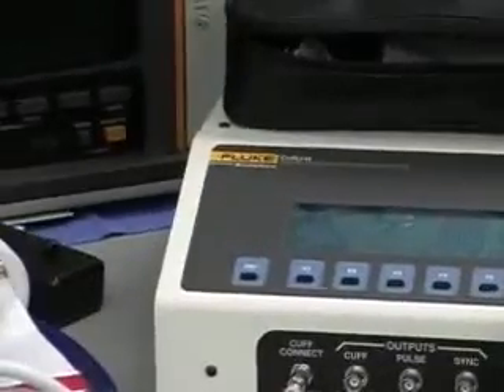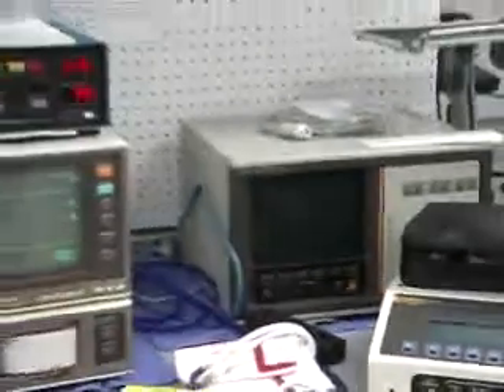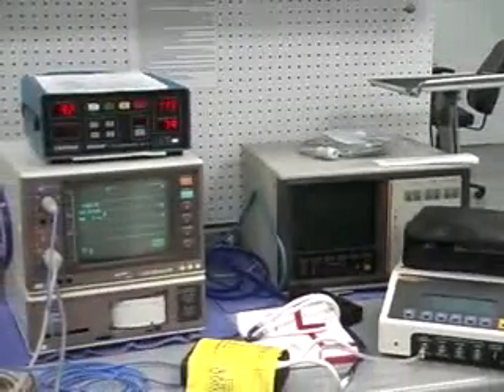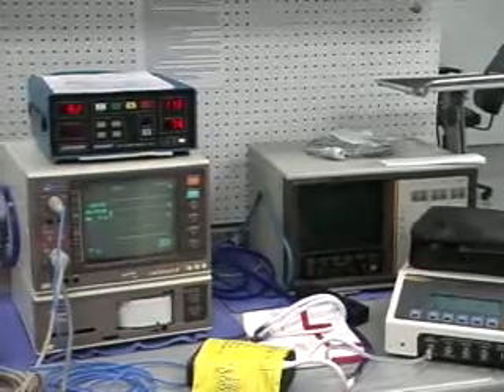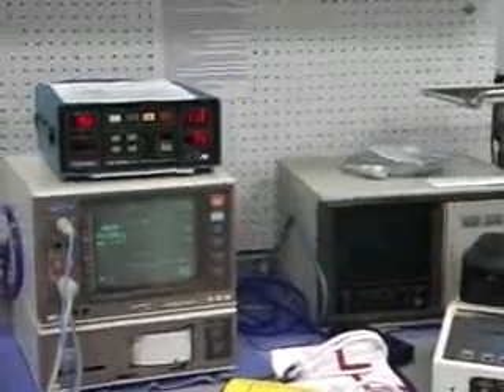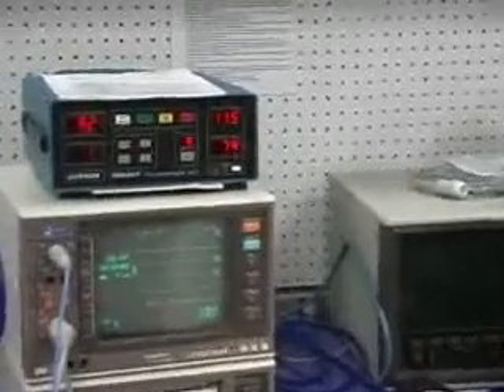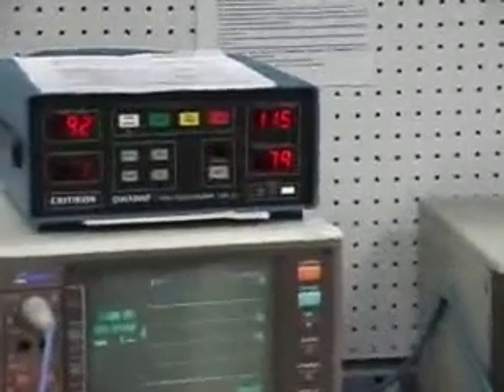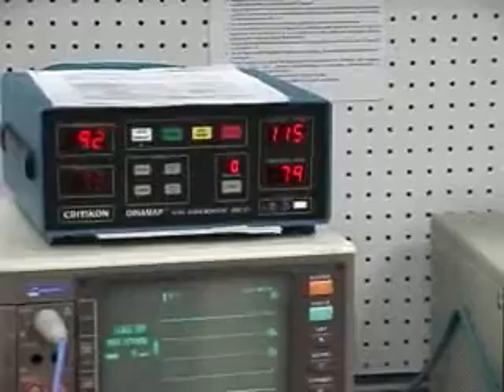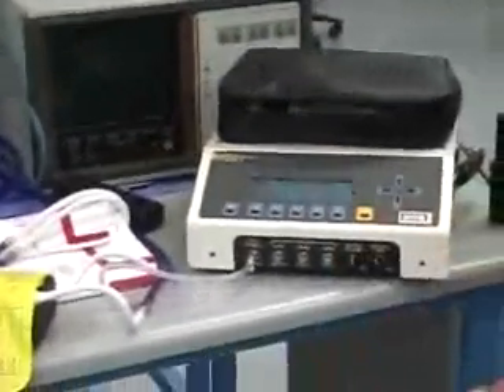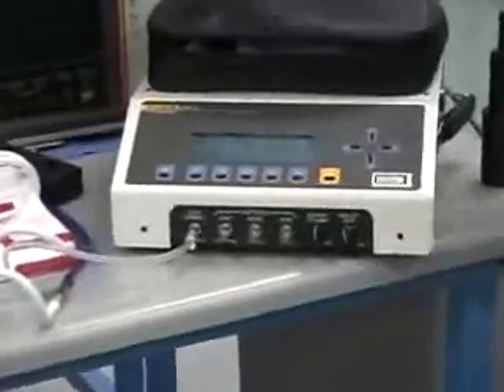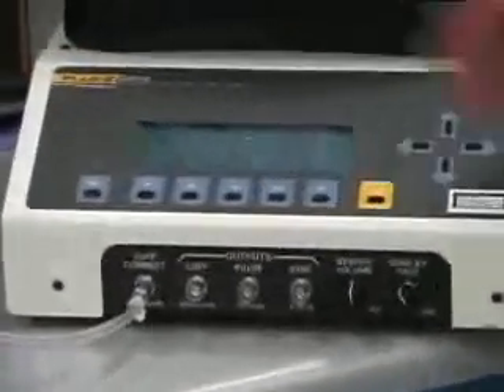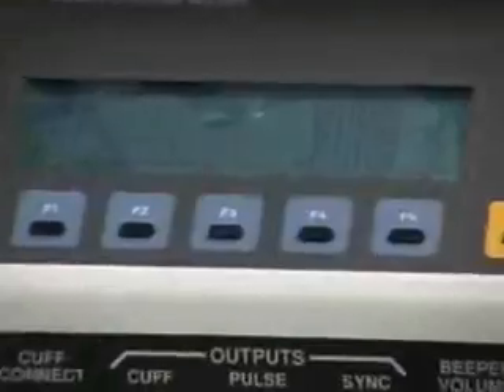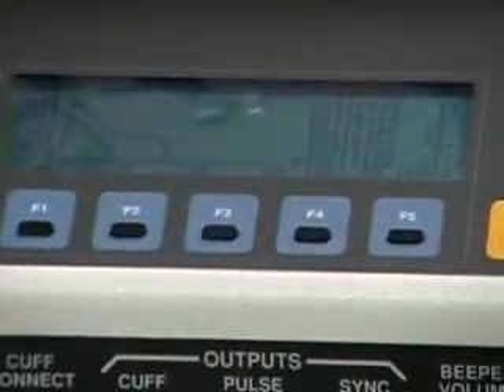Now, it still works very well. You still get a reading of 115 over 79 for 120 over 80, and you get a MAP of 92, which might as well be normal. That's very good. But as you can see, the total test time is 31 seconds. It's a long time to have a cuff on your arm, but with a patient with that type of problem, you would normally see that amount of time.